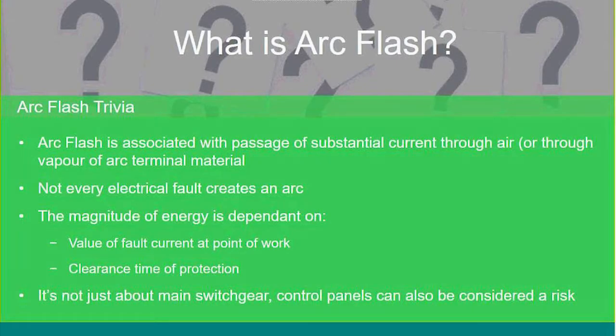So what is it? It's associated clearly with the passage of a substantial amount of energy through air or through terminals, through insulating materials, and I know that sounds very bizarre, but anything that could possibly create a substantial rise of current. So in our world, this really is faults. Whether that's a failure of a piece of equipment, whether that's somebody unfortunately creating the fault in the first place, whether it's a breakdown of insulation on some particular piece of equipment. It could be a number of different things, but we're talking about a very, very high value of current passing. Not every electrical fault creates an arc. As I've said before, some are electrical faults which are leakage currents, which will not create sufficient energies to create the magnitude of energy that will create this arc.